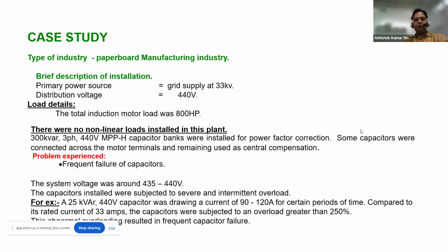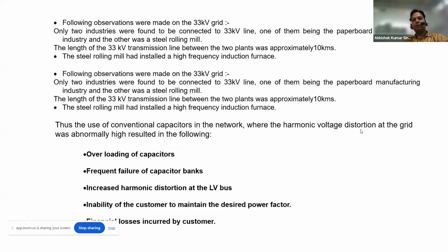basically what they found is that there is an industry near them, which is a rolling mill industry, and there is a furnace there which is producing a lot of harmonics. That harmonic was basically attacking the capacitor. How? When you place a capacitor without any reactor, if you have heard about Xc equal to 1 upon 2 pi fc, when the frequency increases, its value will decrease. Xc is a sort of resistance, so that resistance gets very low. Harmonic current always tries to find the least resistance path, so it was finding that path. That's why the capacitor was failing.